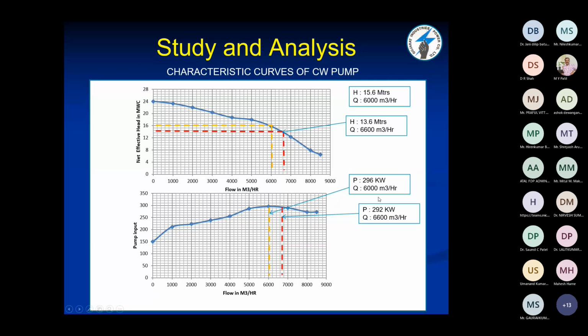This is the characteristic of that pump. You can see at the head of 13.6 meter the flow was 6,600 meter cube per hour, and at the head of 15.6 meter the flow was 6,000 meter cube per hour. In the same condition, the power consumption was 296 kilowatt, and at this level the power consumption is 292 kilowatt. So the power consumption remains almost the same, but there is the reduction in the flow.